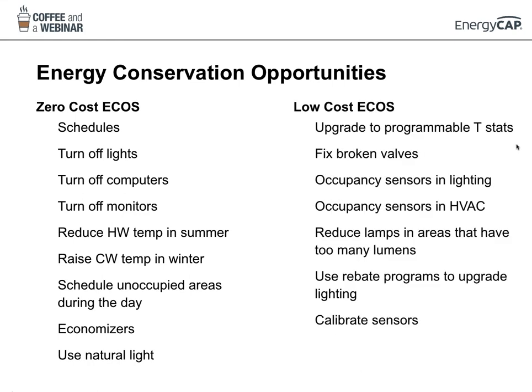Here are some of the low-cost opportunities we focus on: upgrading or programming thermostats, fixing broken valves and sensors. We've done lamp-reduction projects in some buildings where we had too many lumens - we took out a third of the hallway lighting while still having enough lumens, reducing energy use by a third in the hallways.